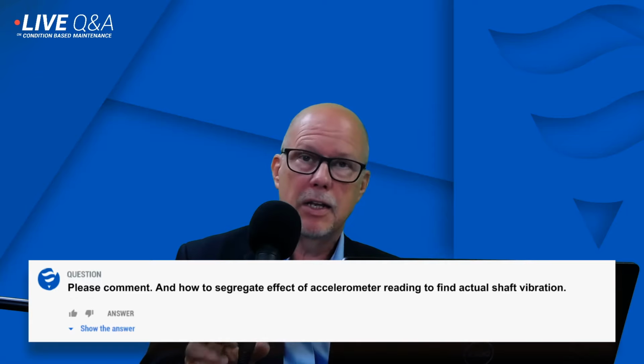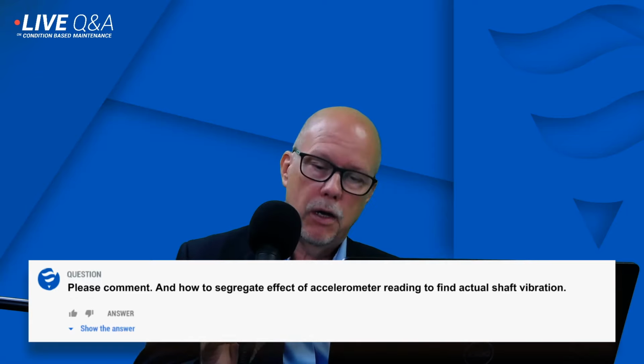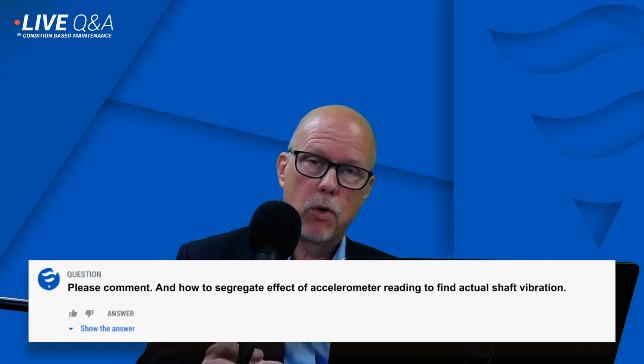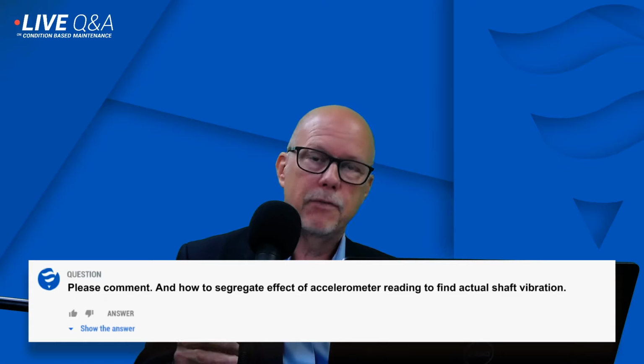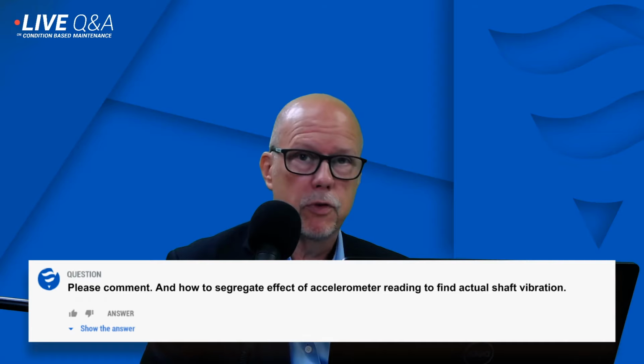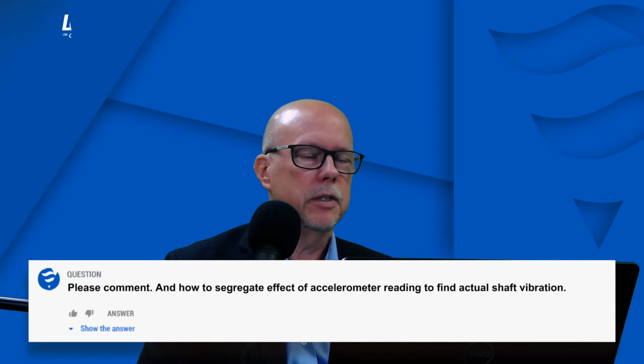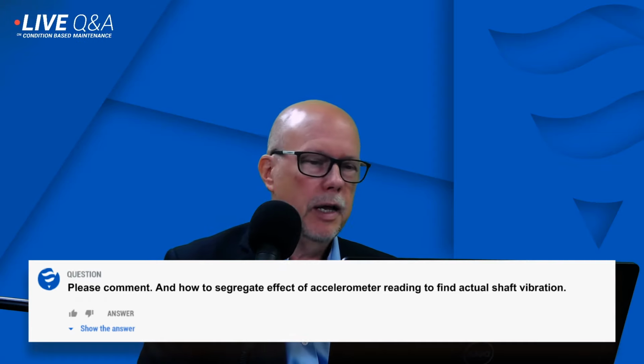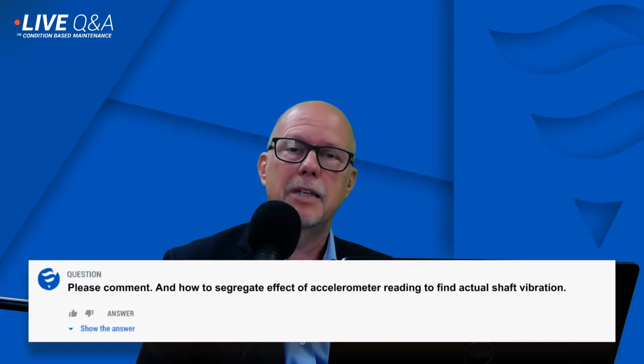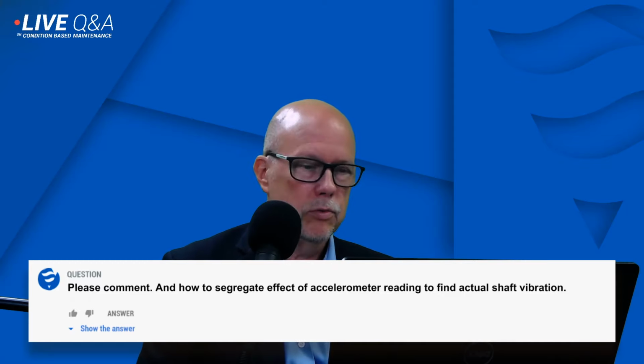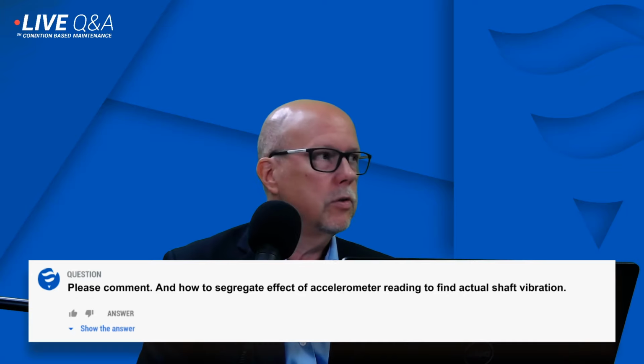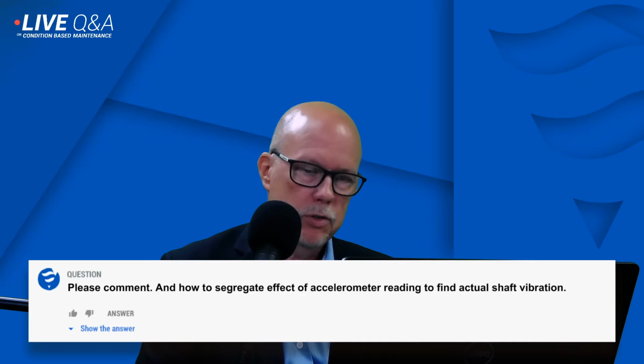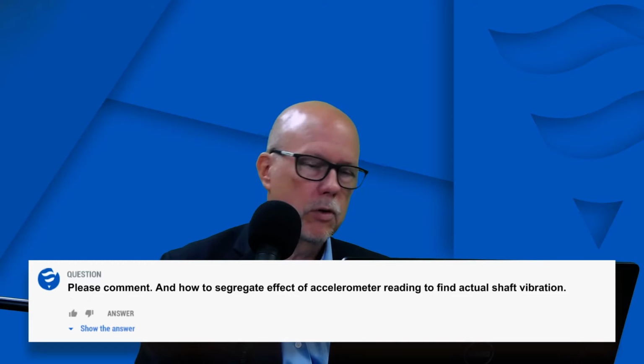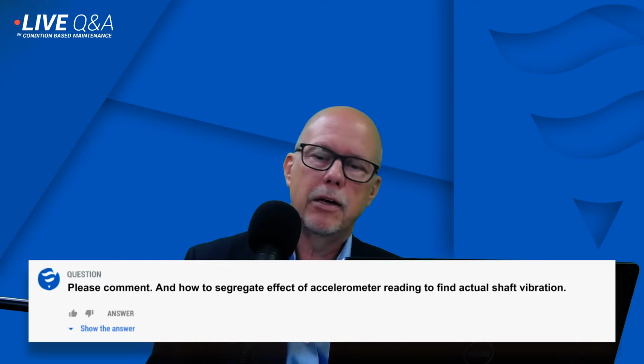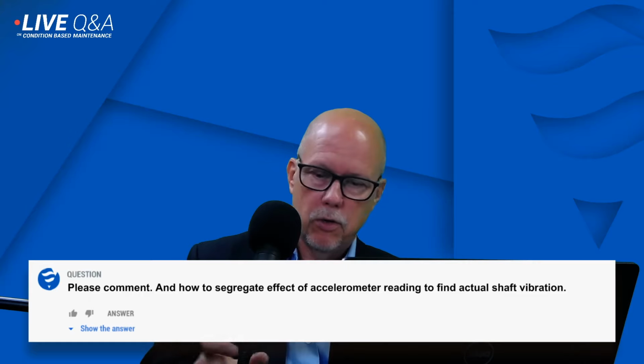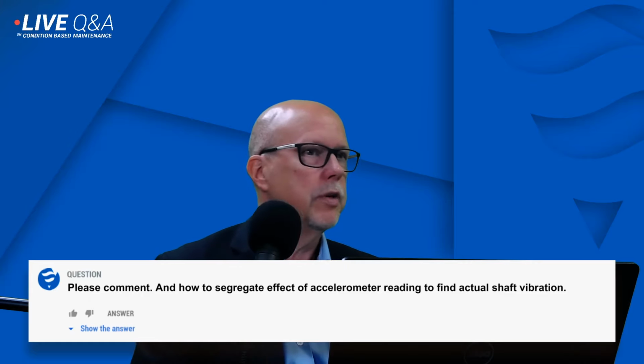And if that is allowed to remain, you'll have some issues between the core and the key bars, and you might have some arcing between the core and the key bar, which of course is very damaging. That's high intensity discharges, and you can seriously damage the core if you allow that to go on. So a combination of two sensors on the bearing housing or on the stator core and frame allows you to see if they are working together or if there's some kind of looseness issue there.